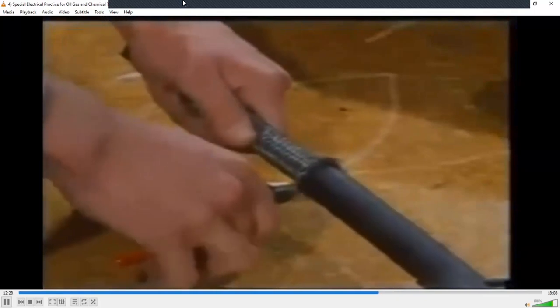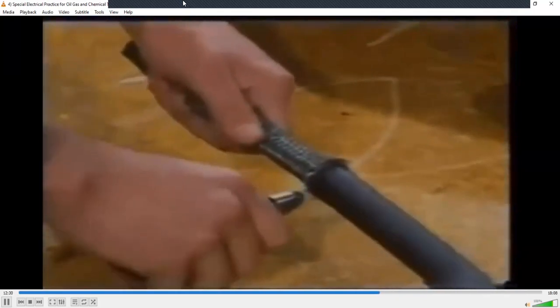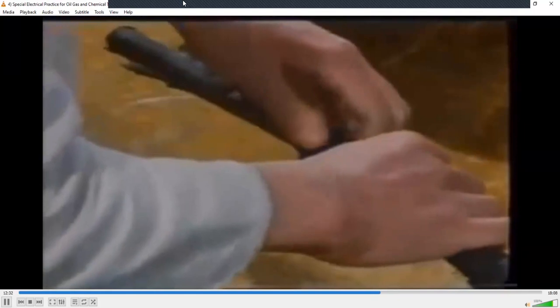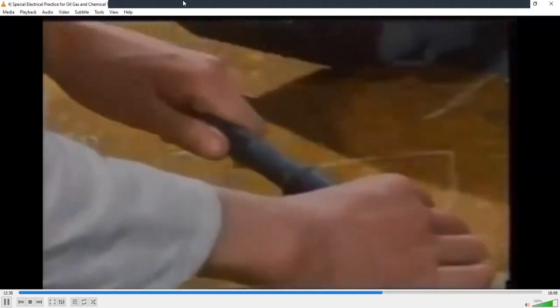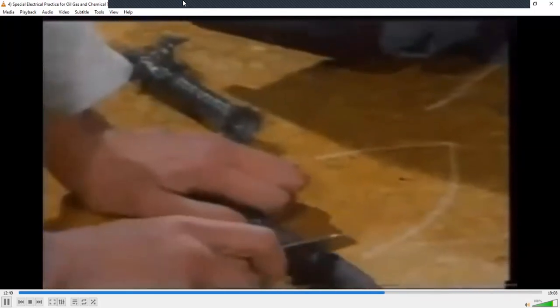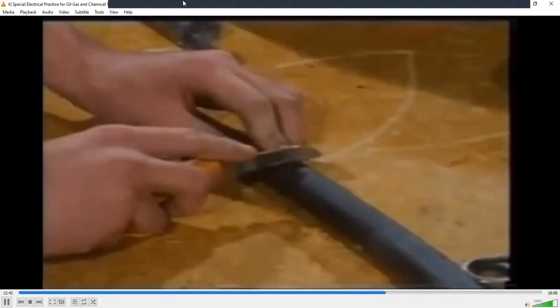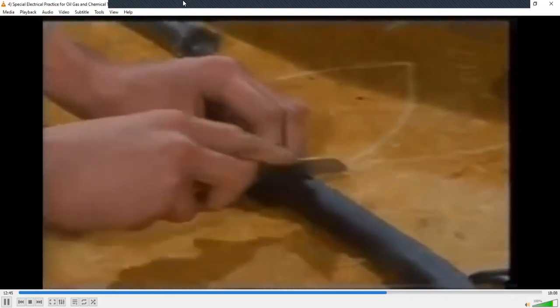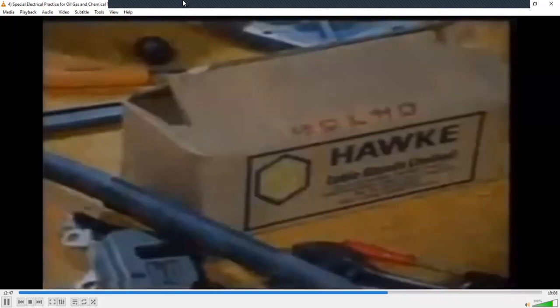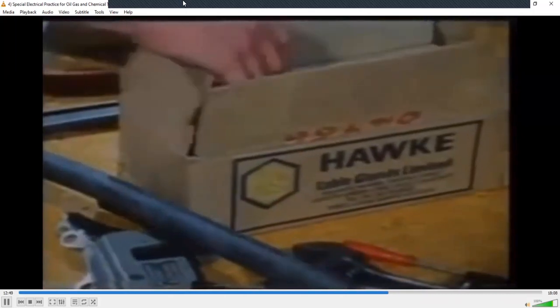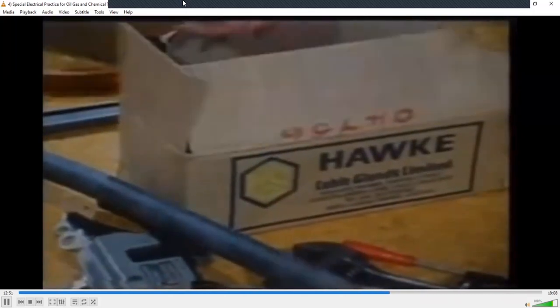The armouring is then cut round with a wire cutter and pulled off. A further short piece of the outer sheath is stripped back, as you see here. This will free a further length of armouring, which will be clamped between the double rings of the gland for tight and secure fitting.